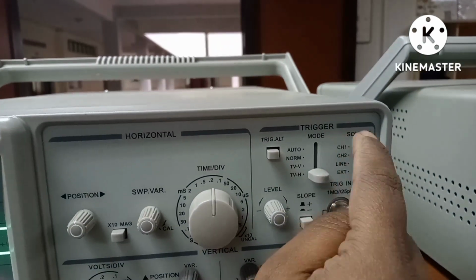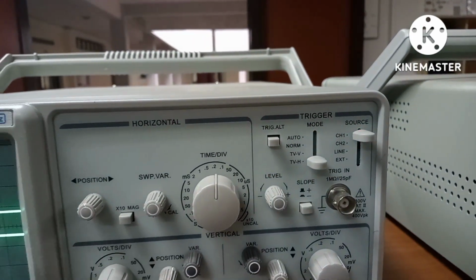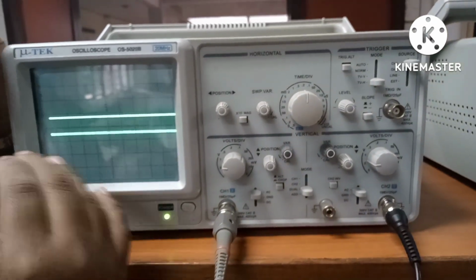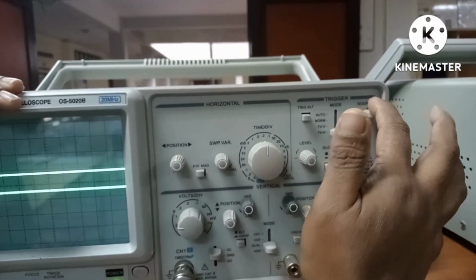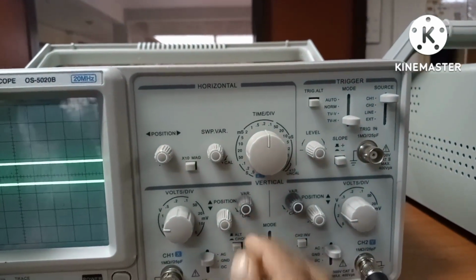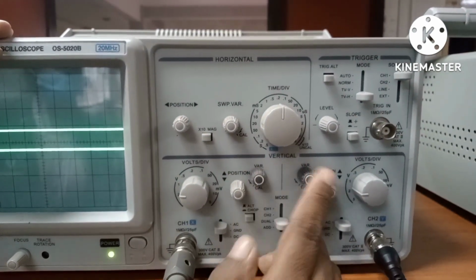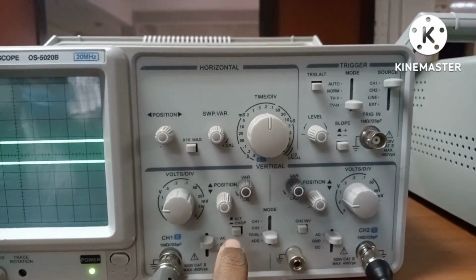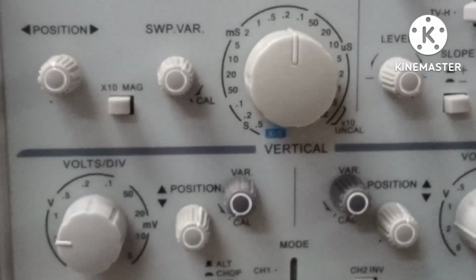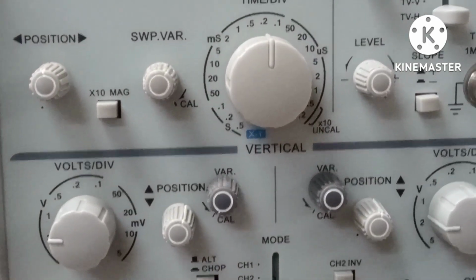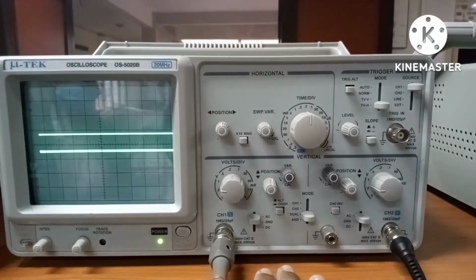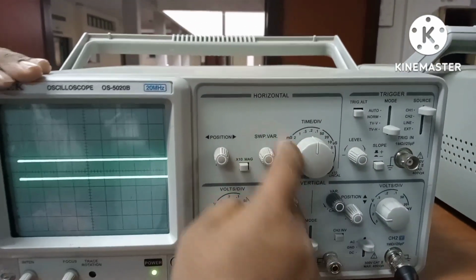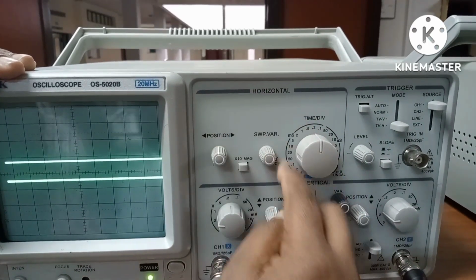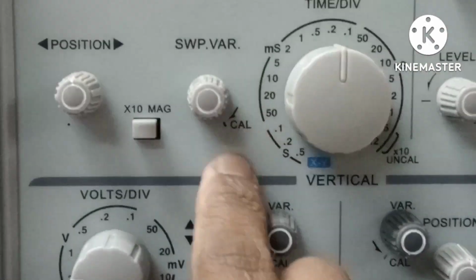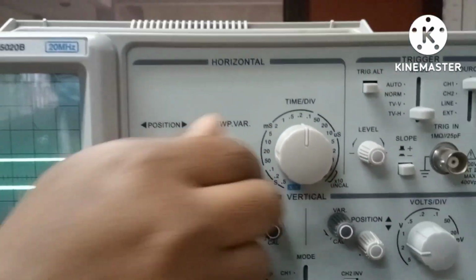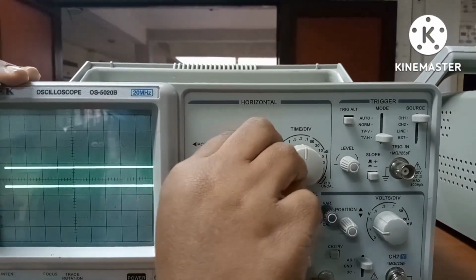And these knobs are used for triggering pulses, meaning triggering to stop the waveform. Sometimes the waveforms will not be synchronized, and for that purpose we use these two knobs to stop the waveform. And these are all the variable positions. Please keep these two knobs in the locked position, or else whatever magnitude of amplitude of the voltage or signal you are varying may differ from your input or output. And this is the sweep variable knob, where you can see the arrow mark for calibration; it has to be locked. Otherwise, if this varies, the frequency of the signal will also vary.